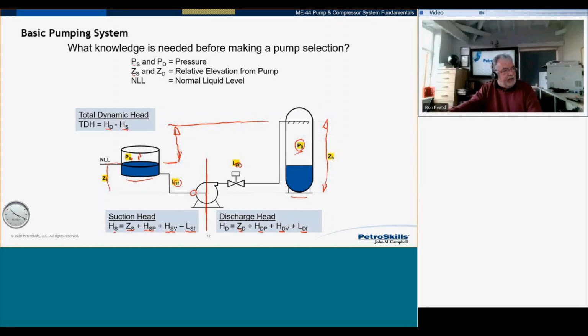But now notice I'm adding the friction losses. I'm not subtracting, as we did over here. That's because we're measuring the amount of energy that the pump has to put into the liquid at the discharge. And because we're at the start of the pipe here, we have to overcome those friction losses, so they're all additive. Now, if we've got that, we've got a lot of information.